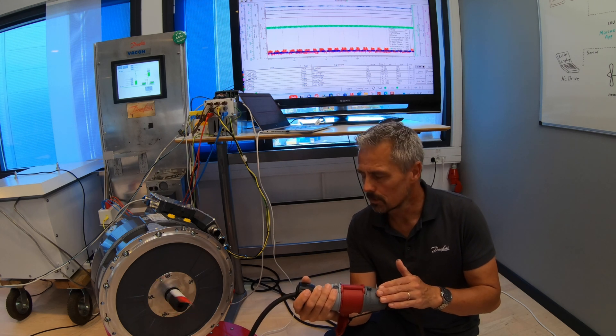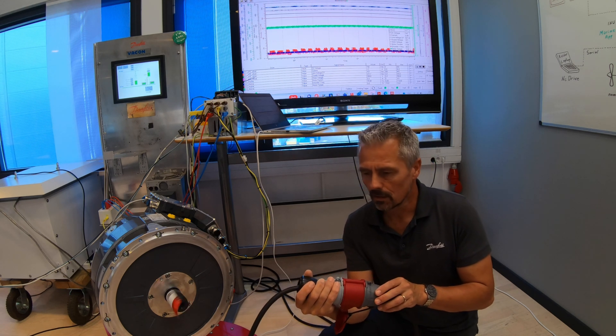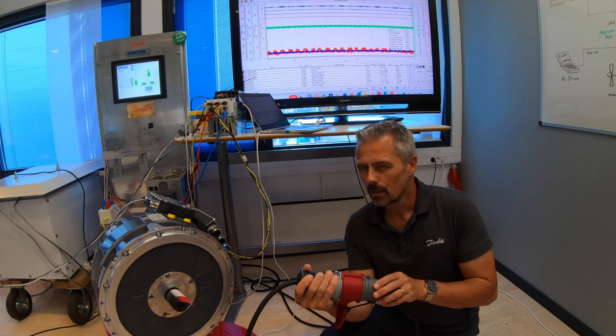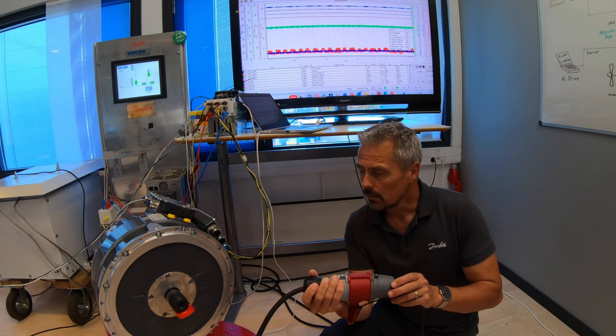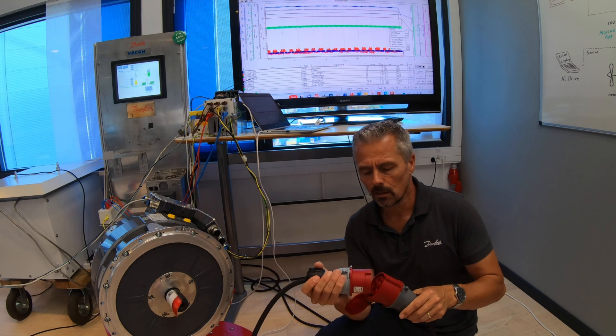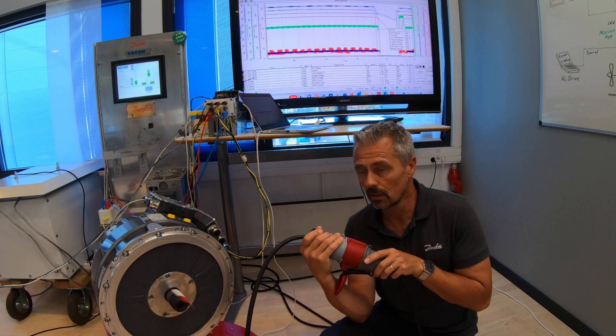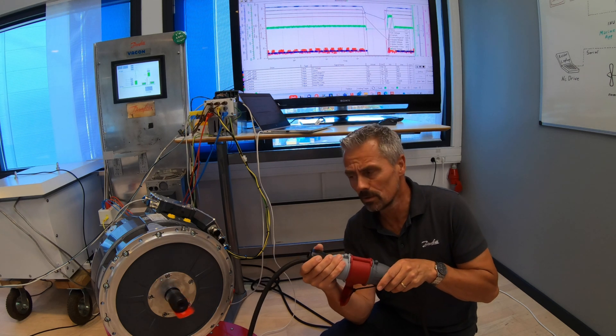On DP class 2 ships there is a requirement that critical functionalities like thrusters, maneuvering, dynamic gangways and stuff, they should continue running even though there is up to a 2 second power blackout. And there should be no need for reset from PLC or humans or anything.